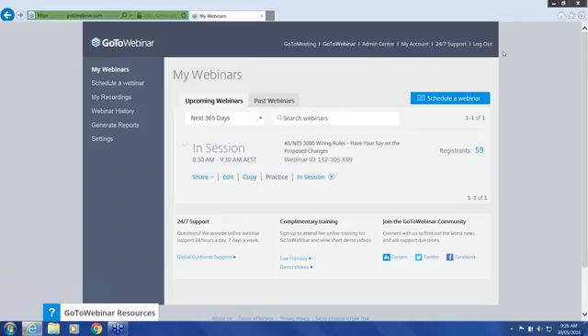For verification, there are some new clauses on extra low voltage testing, a subset of low voltage testing. But the main area we've had questions on is earth fault loop impedance tests, with the common question being when or where you have to do so.